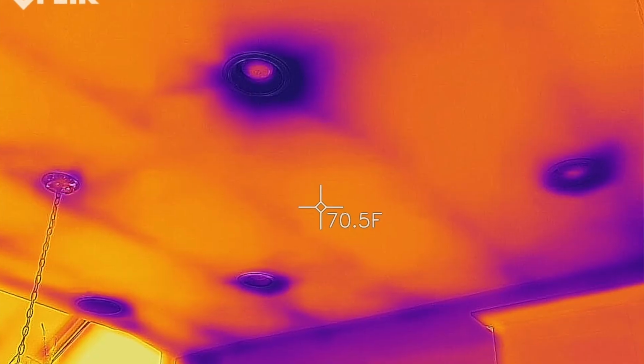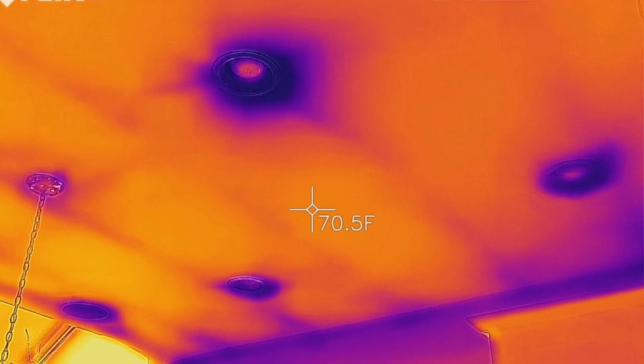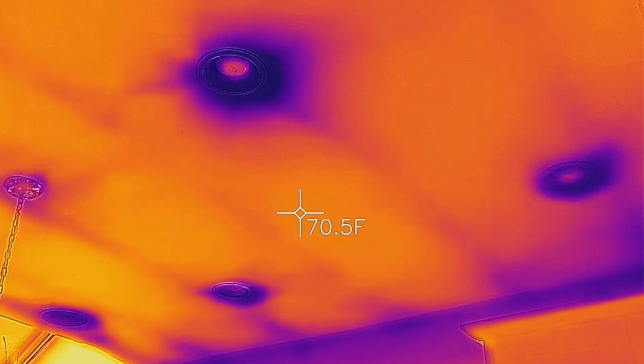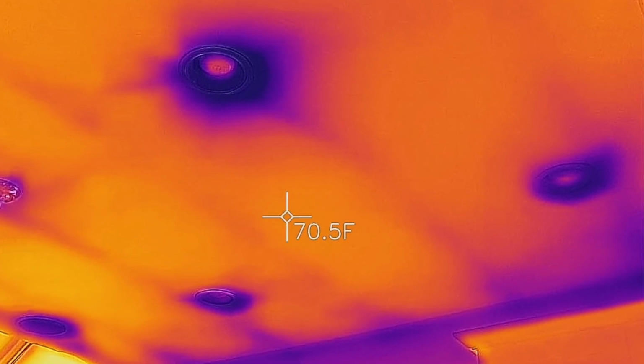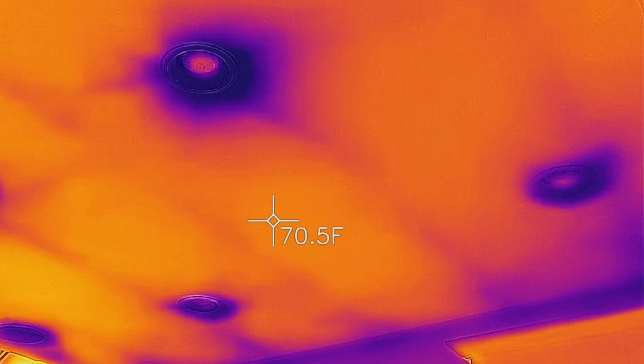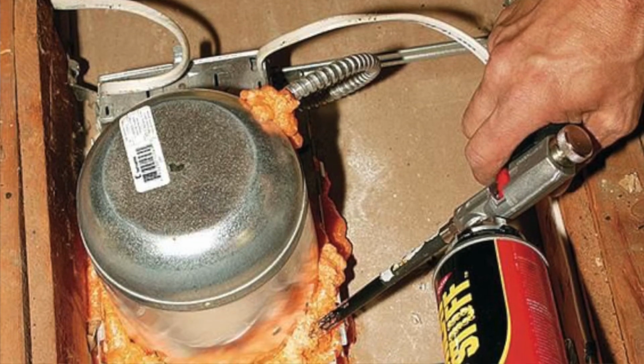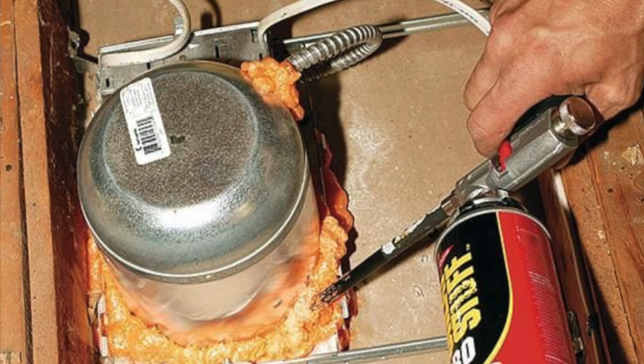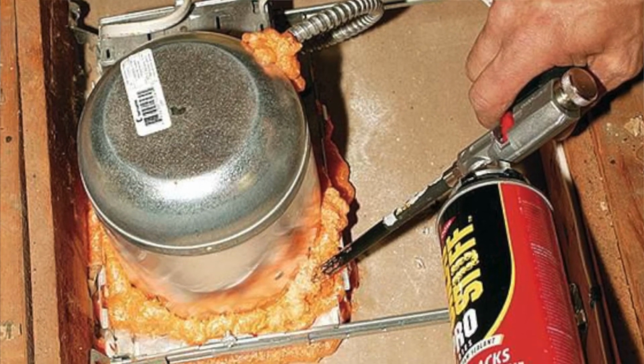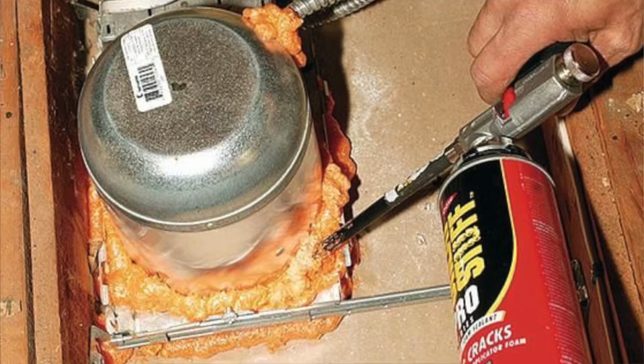into the attic space. So let's say you've got a big open floor plan main floor with scissor trusses and a bunch of can lights in there. Maybe you put a bunch of blown-in cellulose or fiberglass on top of that stuff. There's still a lot of potential for air leakage to come back down through the light assemblies. So we're running the blower door test. Maybe you've kind of got 1, 2, 3 of these different things all going at the same time.